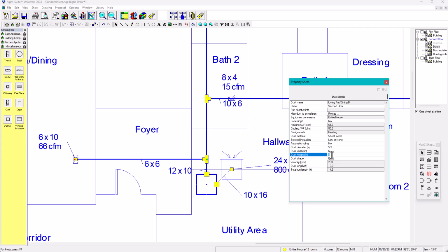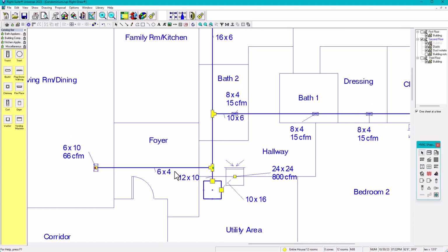usually in commercial this does have a big impact. Like for example, if you have a multifamily home, a lot of apartment units, so you have 50 units, so they try to optimize the ducts, right? But in a home it's okay, but in this case we're gonna put 6 by 4, and what we have is bigger velocity, see, 394. All right, so this is gonna be 6 by 4. We're all good with this.